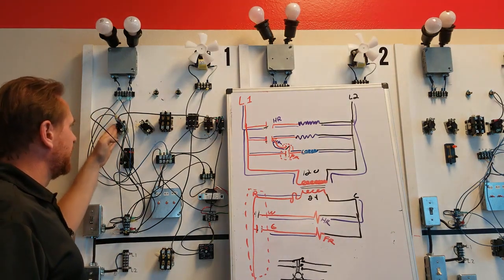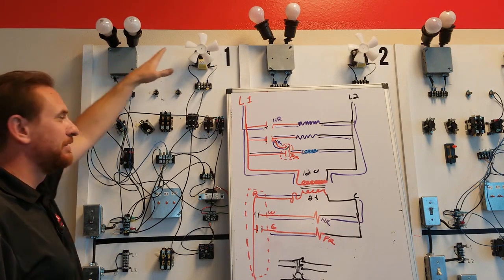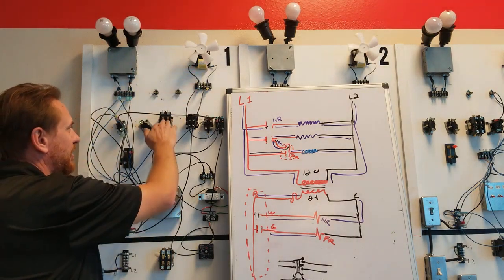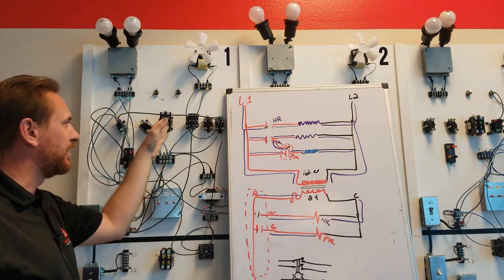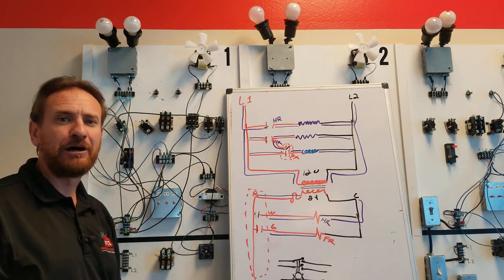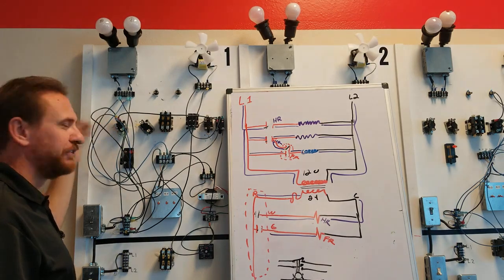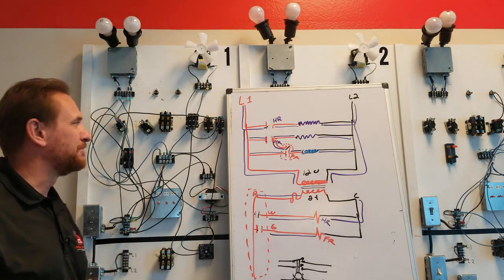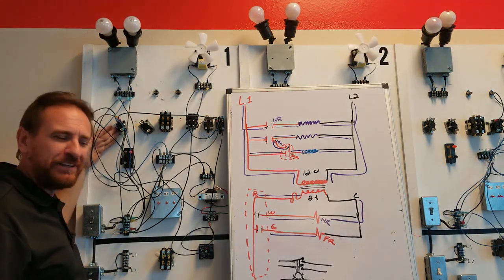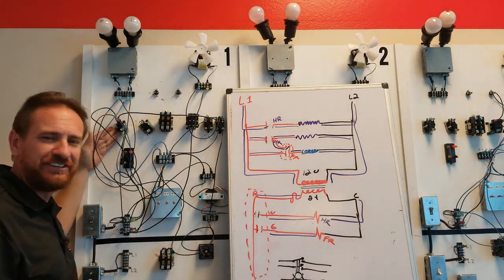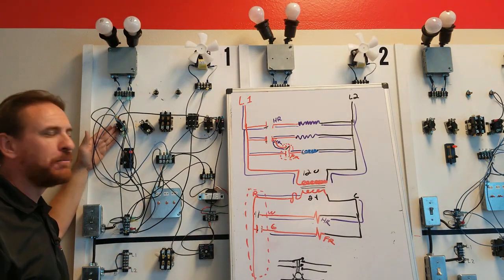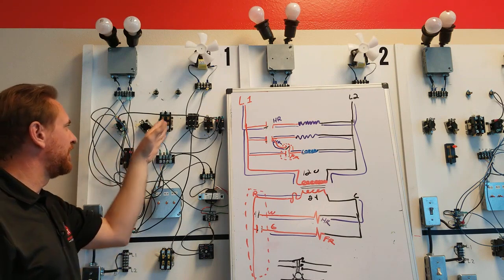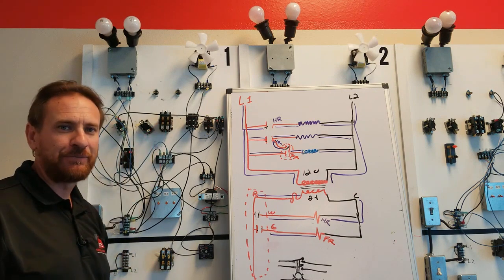So a sequencer controls my heat elements and my fan just like I can with the contactor. Sometimes you'll see them use contactors. American Standard and Trane is a very popular brand, and a lot of other ones will use sequencers. Here's what's important. What did the manufacturer decide? What did that engineer spend all of his career designing? We're going to go back with that. If the contactor was there, that's what we're going to go back with.